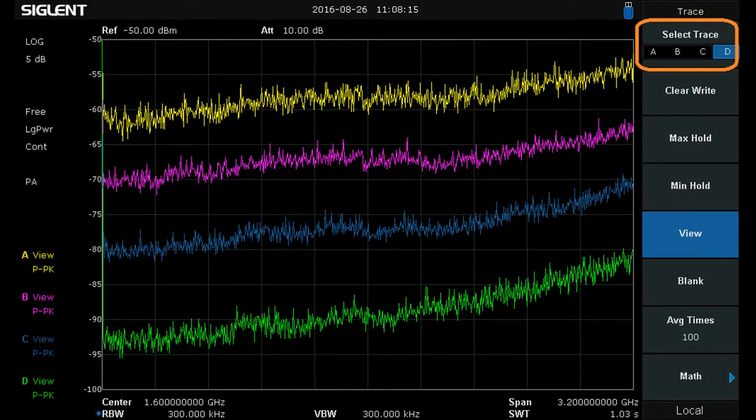This is four versus the three that is available in many other spectrum analyzers. Having the ability to view four traces simultaneously and being able to configure them each separately allows you to compare more of the traces that you've collected using different setups for the instrumentation or any particular parameters that you may have adjusted while you were performing the data collection.